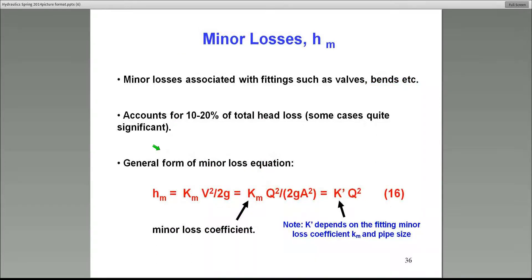Minor losses. These are due to fittings and pipes normally. And most of those fittings, the head loss can be associated with those fittings, can be expressed in this form. K_m, V squared over 2g, where V squared over 2g is the velocity head. K_m is basically the minor loss coefficient.